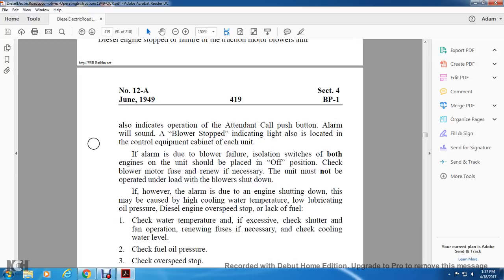For an alarm due to blower failure, the isolation switch of the engine of the unit should be placed in the off position. Check the blower motor fuse and renew if necessary. The unit must not be operated under load with the blower shut down. If, however, the alarm is due to the engine shutting down, it may be caused by high cooling water temperature, low lubricating oil pressure, diesel engine overspeed stop, or lack of fuel.